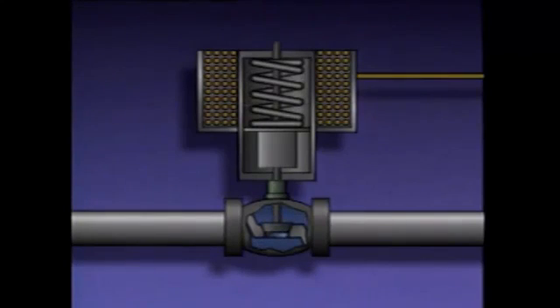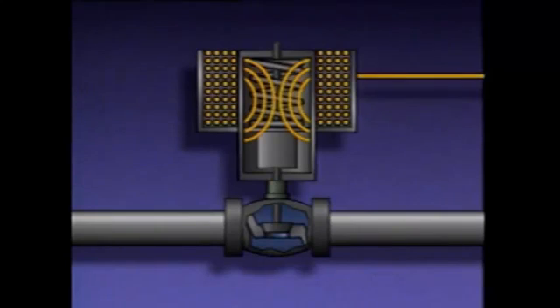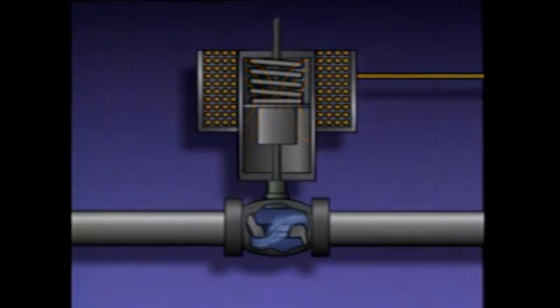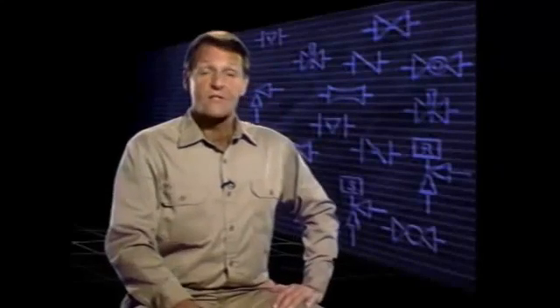When current flow starts or stops, the movement of the armature is almost instantaneous. When current flow starts, the actuator will fully open the valve; when current flow stops, it will fully close the valve. There is no intermediate or in-between position, so there is no way for a solenoid actuator to throttle a valve. Since most solenoids operate this way, they are typically used with on-off valves.